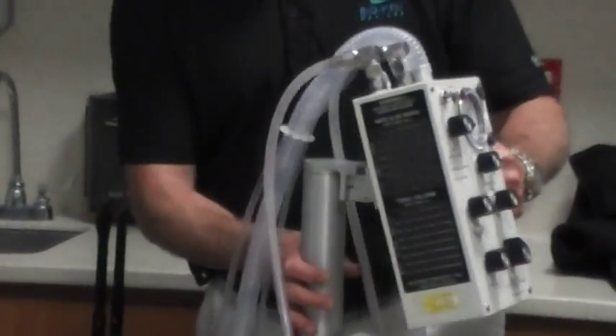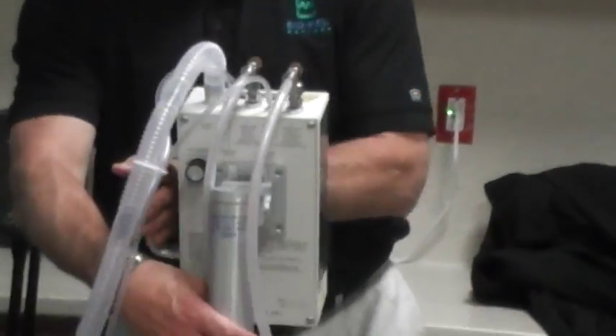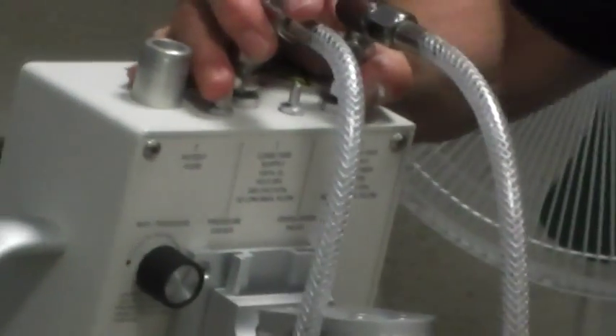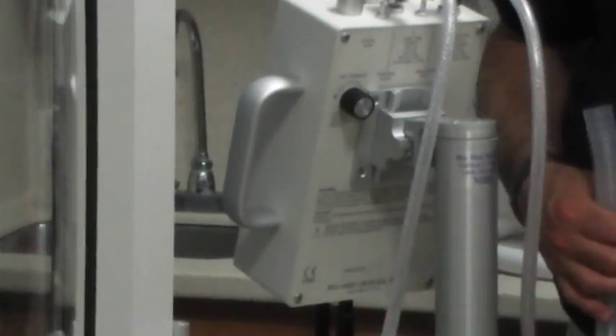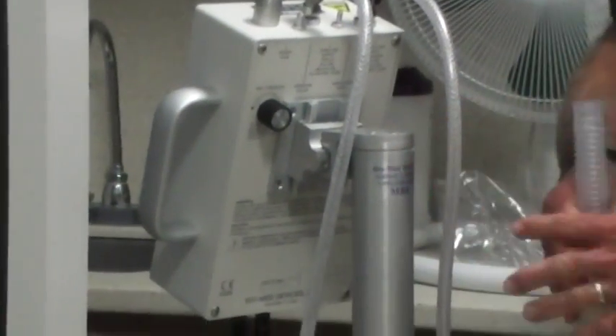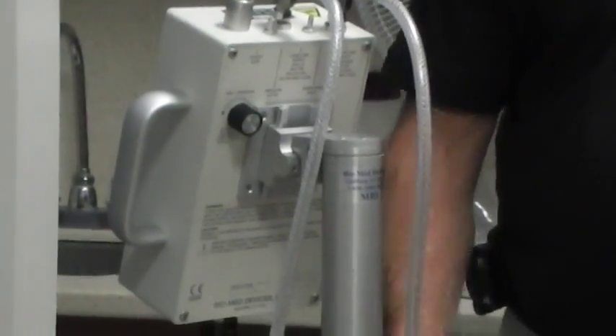Okay, so if you look behind the vent, I'll show you. The vent is all pneumatically powered, so we're actually running this thing off of 100% oxygen. Then we're using the blended source for the patient supply.